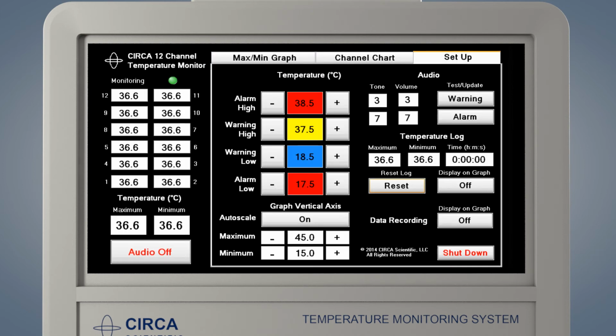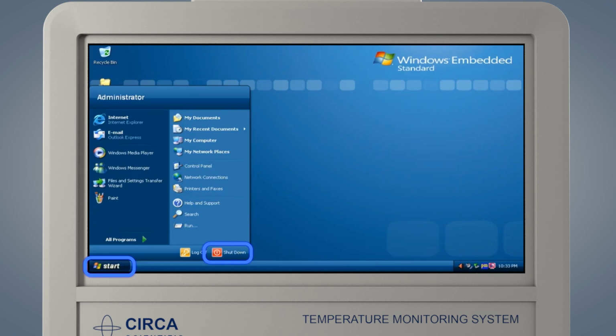At the end of the procedure, disconnect the interconnect cable from the probe and slowly remove the CircaS probe. The CircaS monitor is now ready to be shut down. The power button on the back of the monitor should never be used to shut down the monitor. To properly shut down the CircaS monitor, go to the Setup screen. From the Setup page, press Shut Down. This will close the CircaS software and return the user to the monitor home screen.